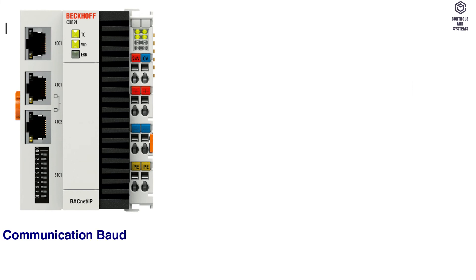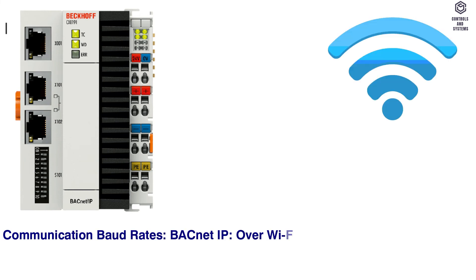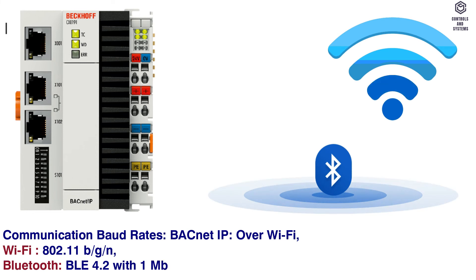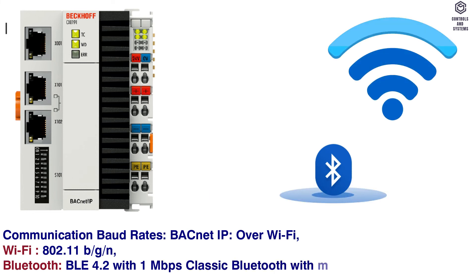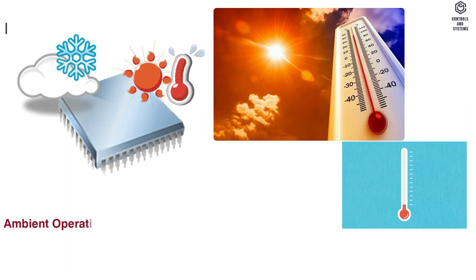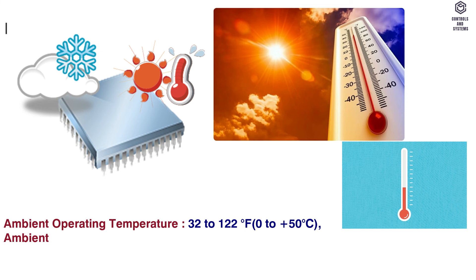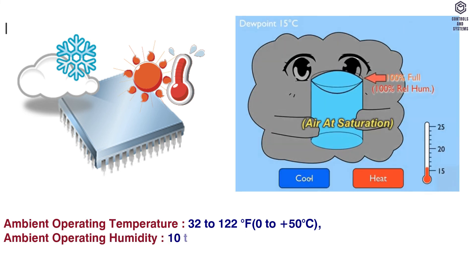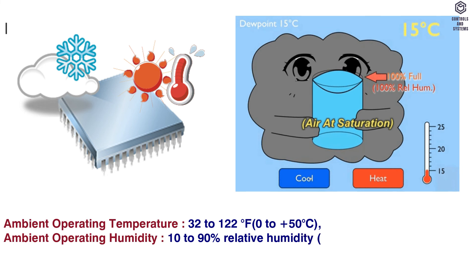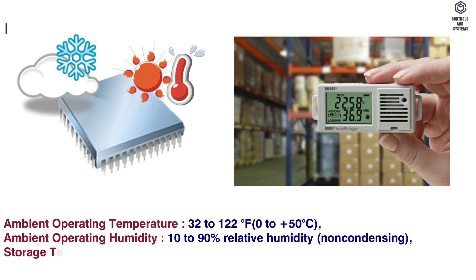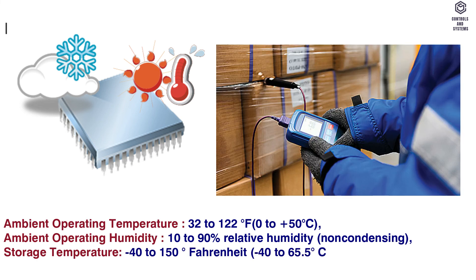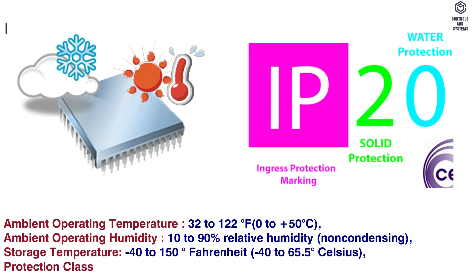Communication: BACnet IP over Wi-Fi. Wi-Fi: 802.11 b/g/n. Bluetooth: BLE 4.2 with 1 Mbps; classic Bluetooth with maximum 3 Mbps. Operating environment: ambient operating temperature 32 to 122°F (0 to +50°C). Ambient operating humidity: 10 to 90% relative humidity, non-condensing. Storage temperature: -40 to 150°F (-40 to 65.5°C). Protection class: IP20.